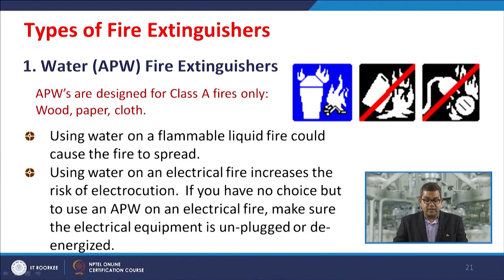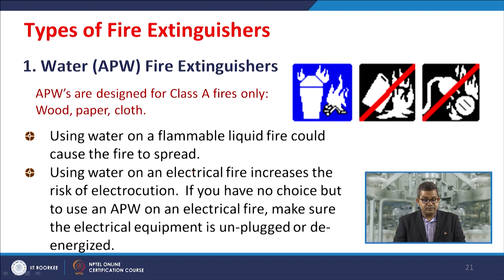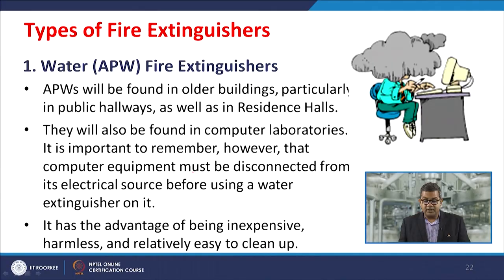APWs extinguish fire by taking away the heat element of the fire triangle through the formation of small droplets. These air pressurized water extinguishers are designed for Class A fires only — wood, paper, and cloth. Using water on flammable liquid fires could cause the fire to spread. Using water on an electrical fire increases the risk of electrocution. If you have no choice but to use an APW on an electrical fire, make sure the electrical equipment is unplugged or de-energized first.